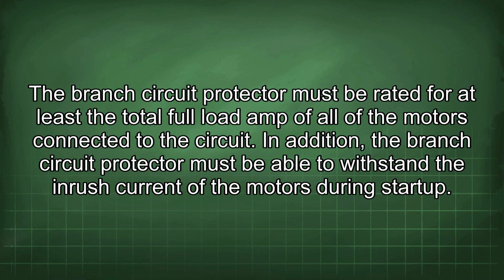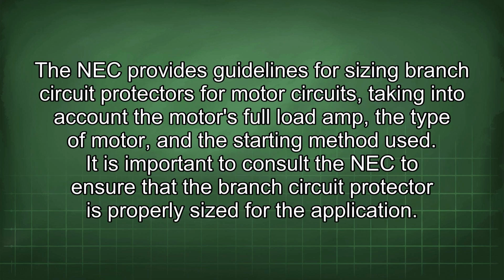In addition, the branch circuit protector must be able to withstand the inrush current of the motors during startup. The NEC provides guidelines for sizing branch circuit protectors for motor circuits, taking into account the motor's full load amp, the type of motor, and the starting method used. It is important to consult the NEC to ensure that the branch circuit protector is properly sized for the application.